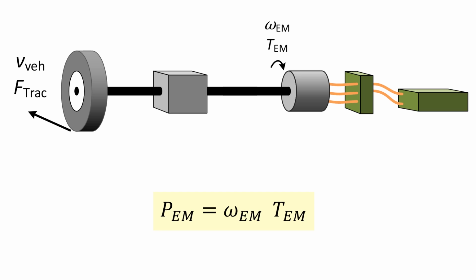There is another advantage of high-speed electric machines, and that is that they typically have high efficiencies. At a constant torque, the losses of the machine typically increase less than linearly with the speed, while the power produced increases linearly. So a machine with higher speed generally has higher efficiency than a similar type of machine for lower speed.